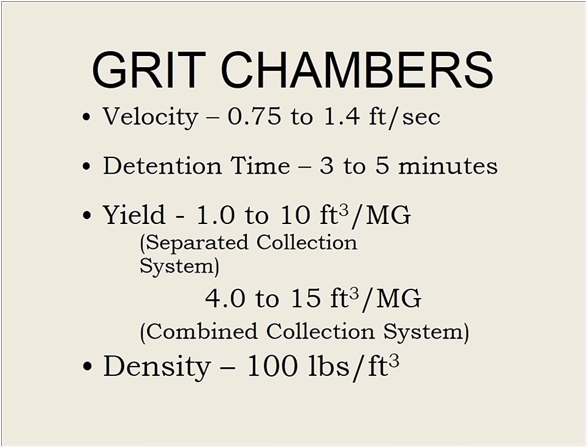So we're actually going to slow the velocity of this water down from our 1.5 to 2 feet per second we had through screening down to about 3/4 to 1 foot per second. We're going to slow it down just enough so that the dense material can settle, but any organic material, which is still lighter, can stay in suspension. We don't want that settling out. That has to go to the bugs. About 3/4 to 1 foot per second. Cut that to 1/2. We do that by expanding the area of flow.